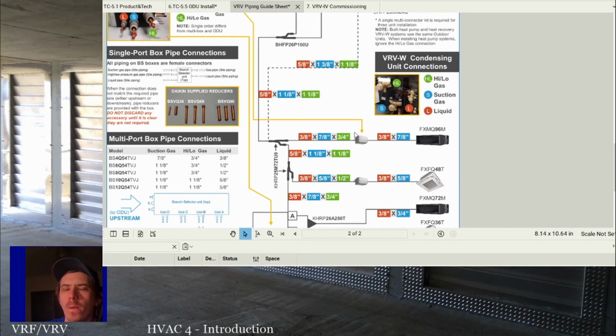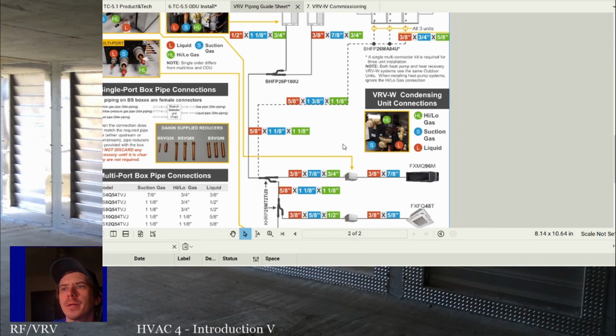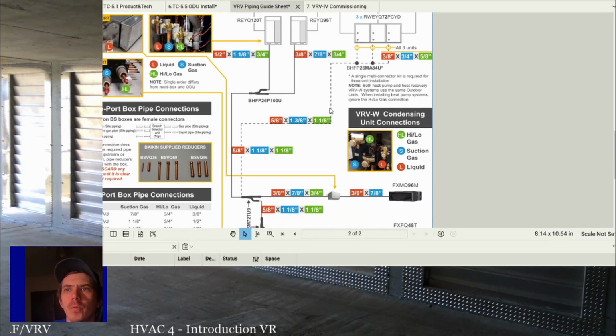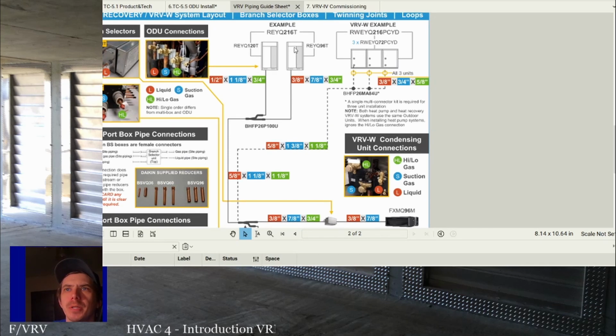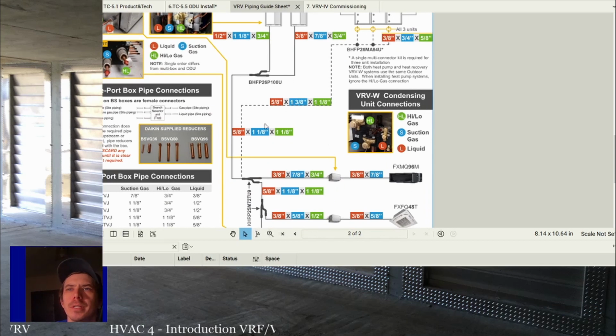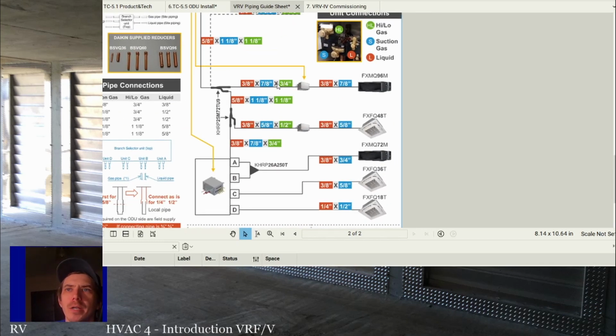But communication is pretty much the same across all manufacturers except for the type of wire they spec. For the most part, it is 2-wire, stranded, daisy chain through the system. And what do I mean by that? Typically you're going to have a situation similar to this. You're going to have a wire connecting all your outdoor units. One outdoor unit is going to be the master outdoor unit. That outdoor unit is going to have a communication wire, 2 wires, red and black or whatever, colors don't matter, but basically just 2 wires that go to a branch selector box.